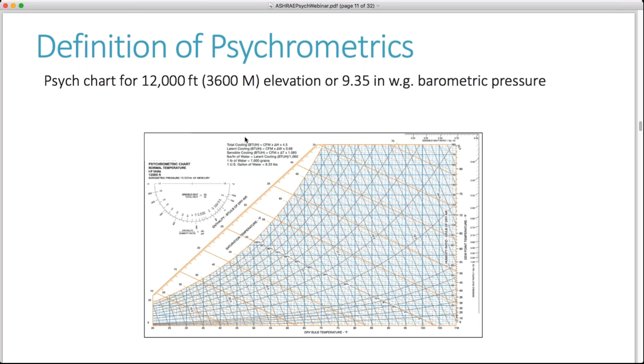However, building designers, say in Denver, which is at 5,000 feet, would have some problems because the density of the air is a lot different up there than it is at sea level, say here in the Bay Area. So if you were indeed plotting processes in Denver using the 0 elevation chart, you would produce inaccurate results. However, with software and apps, you can immediately view a chart, just enter the elevation and it will alter the chart, so it is more appropriate for the elevation that you're at.